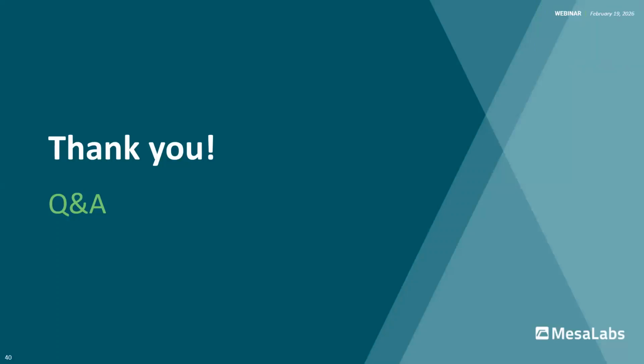Great, thank you. Next question I have is, one of our participants says that calibrating and sampling below 0 degrees Celsius can be challenging. Do you have any recommendations for working in environments below freezing? Depends on how far below 0 Celsius. If you're a reasonable amount below, and I've sampled as low as about 30 below Celsius, pump and calibrator function is all right. Below that, your batteries may start to drop off pretty badly, but the standardization equations still apply if you're doing gas and vapor sampling.